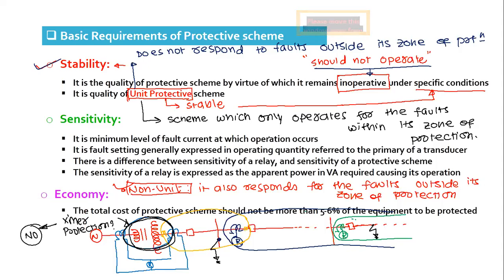To make you understand non-unit, suppose there is a fault here on this line. Now it is in the zone of this relay as well as the zone of this relay. The fault is on this line, so here we will coordinate the relays such that this relay should operate first. If this relay does not operate within some time, then after a little more time this relay will operate.